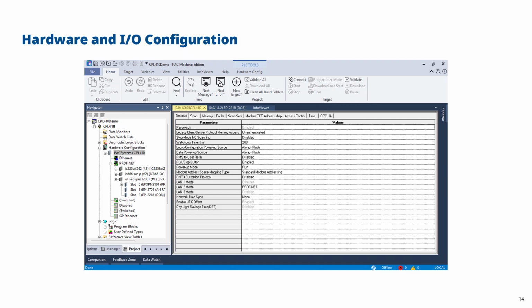Now I've got enhanced security enabled, so I also have an access control tab, and the access control tab allows me to set what memory areas can be accessed externally. So this includes control of OPCUA variables, and it also includes access via legacy protocols to the data table. For example, if I don't want anyone to read outside of, say, register 100 to register 110, I can set in the access control to only make register 100 to 110 read and write, and I can have everything else disabled. Another option is I might have access control with read-only access to maybe register 200 to 210. So I can add that as an access control area for read-only.